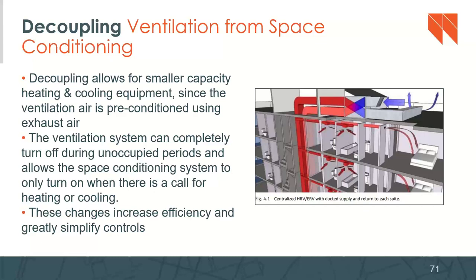So, decoupling the ventilation from space conditioning. We talked about the option to integrate your ventilation system, i.e. your ERV or HRV, into the heating and cooling system. But decoupling is going to allow for a smaller capacity for the heating and cooling equipment, since that ventilation air is preconditioned using the exhaust air of the ERV, right? The heating and cooling ductwork and equipment are not being used quite as much. The ventilation system can completely turn off during unoccupied periods.